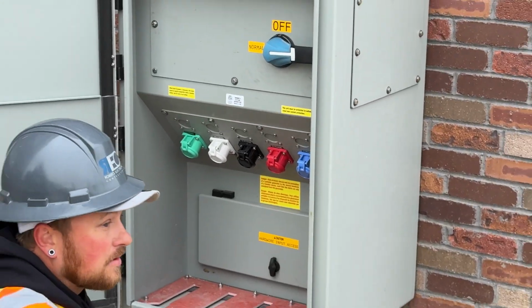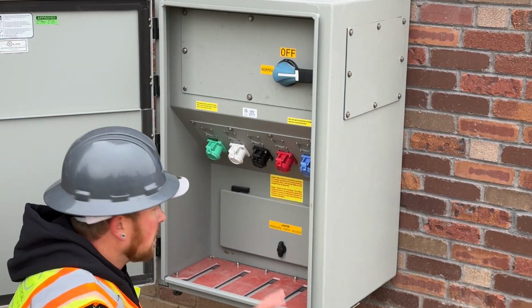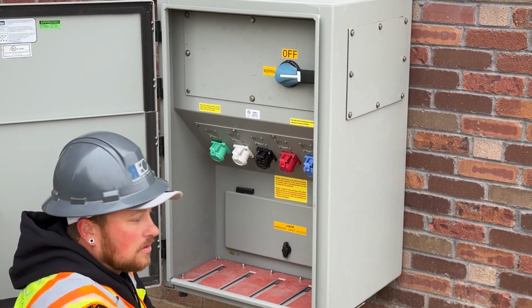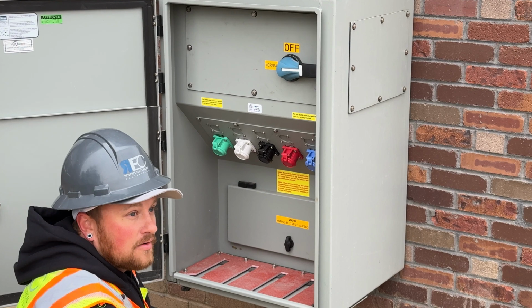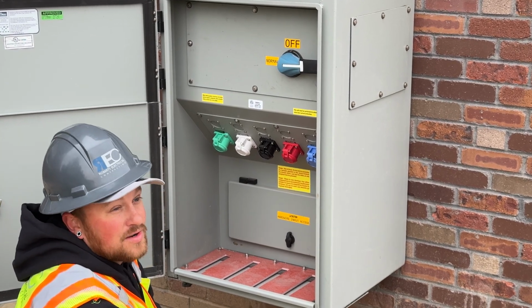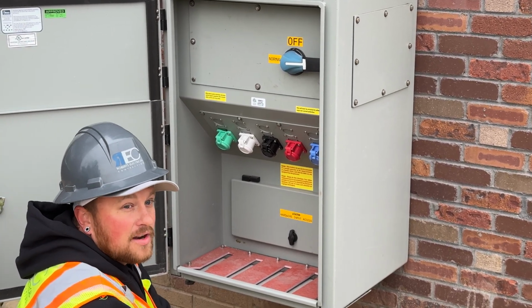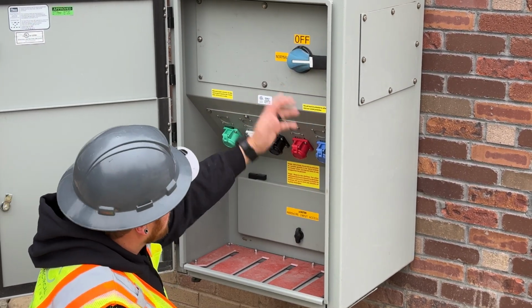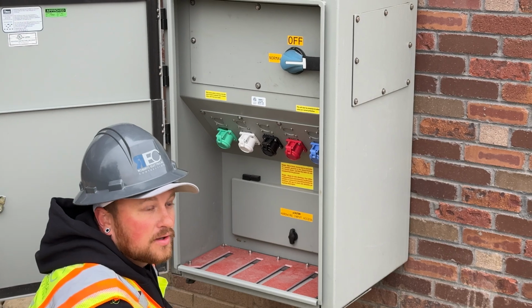EM backup. So say there was a big problem everywhere, this helps keep power onto the building and the emergency areas. You know, lighting in the corridors, elevators stay running. It won't keep the units running because the units are not on the generator. But yeah, you just do that, switch it over to portable, and that'll keep power going through to the EM panel.